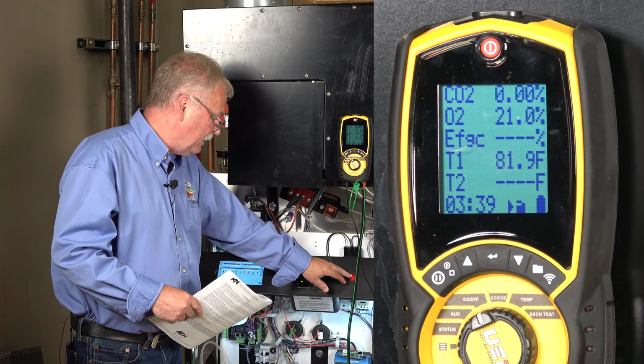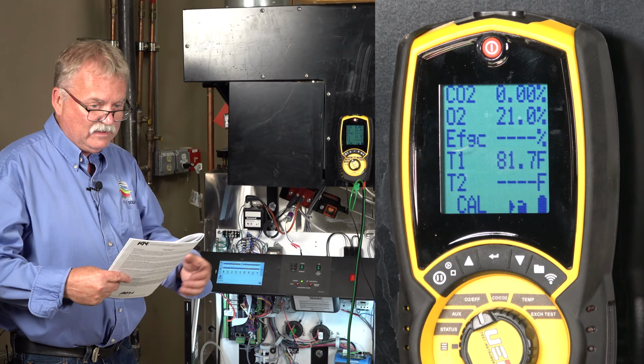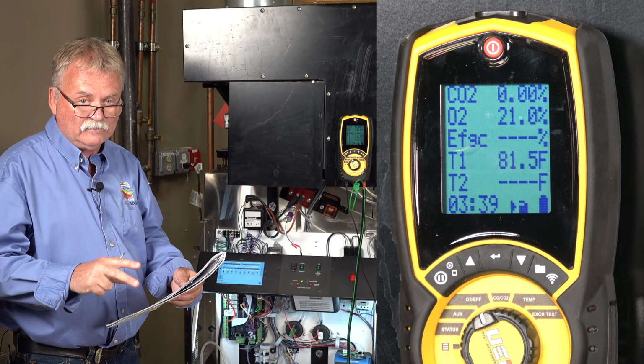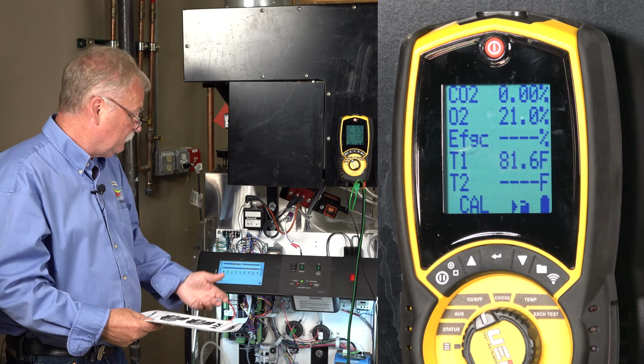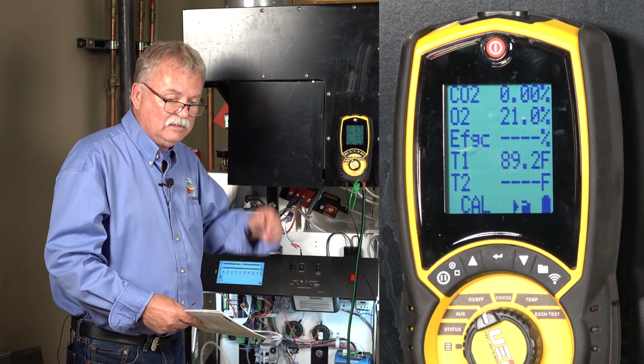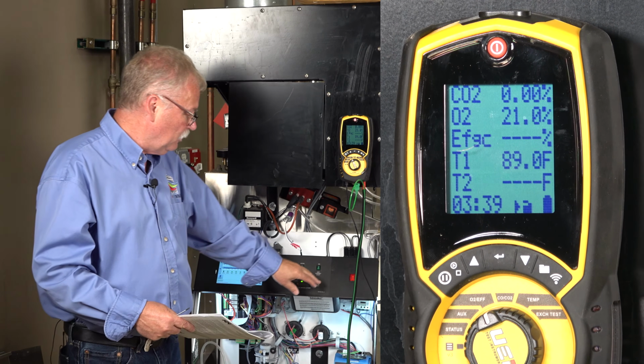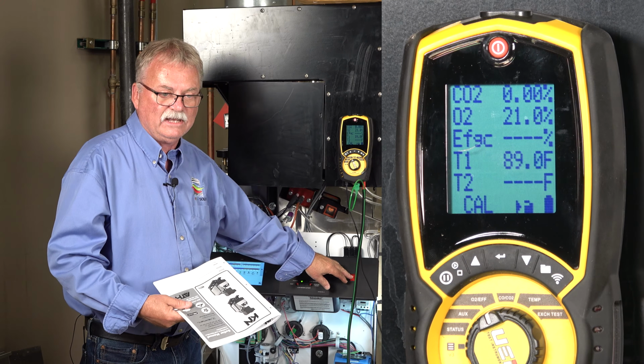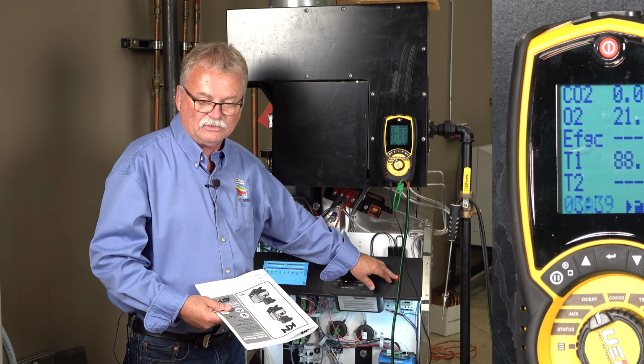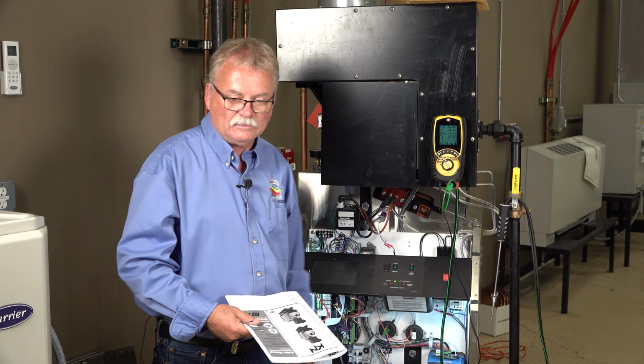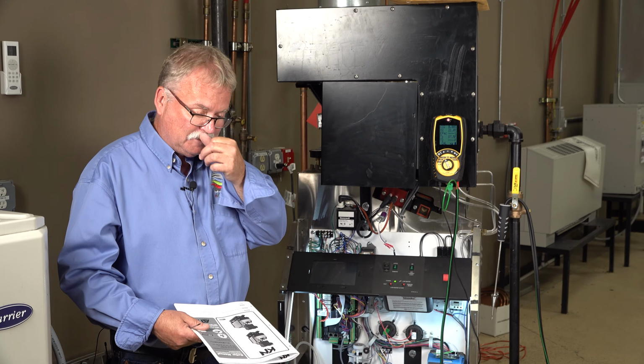If I want, I could try it again. The gas valve will settle in a little bit. Okay, so you can fire it a few times. I normally like to fire a boiler, and this manufacturer likes us to fire it 10 to 15 times after initial combustion settings, just to make sure it fires off quietly and everything else.